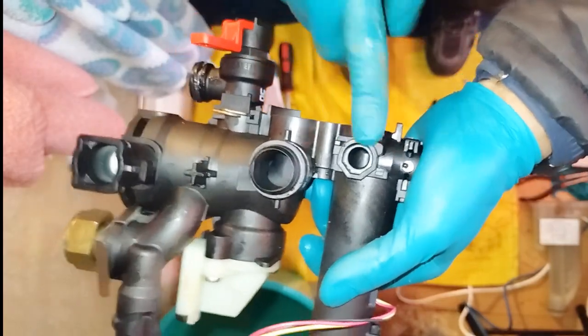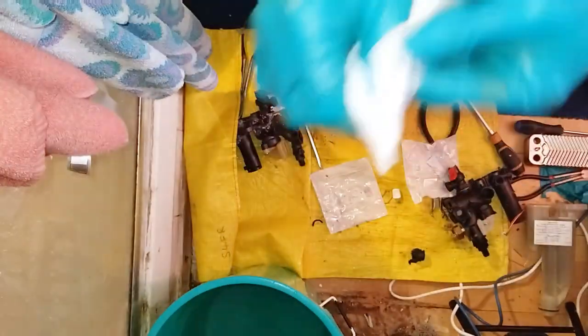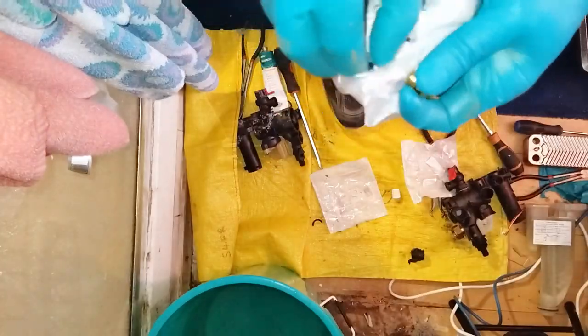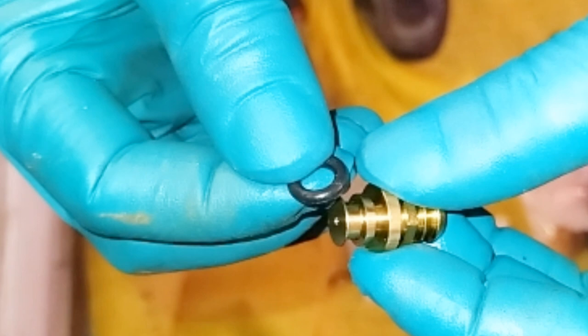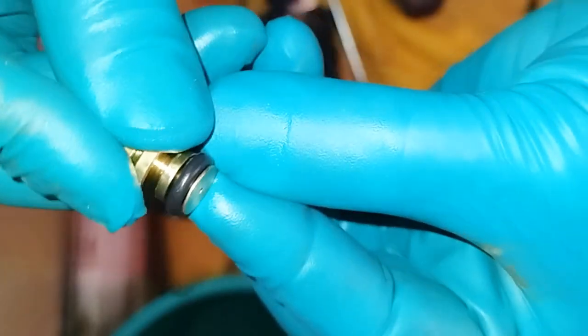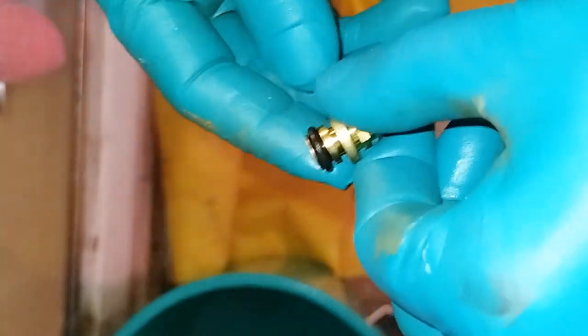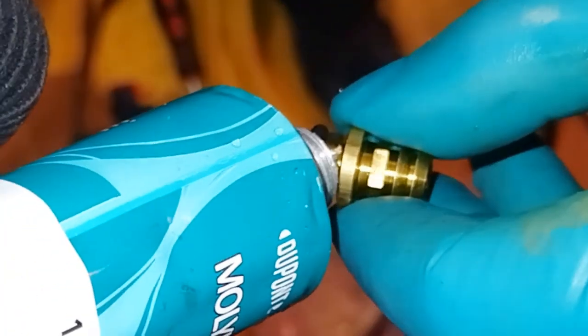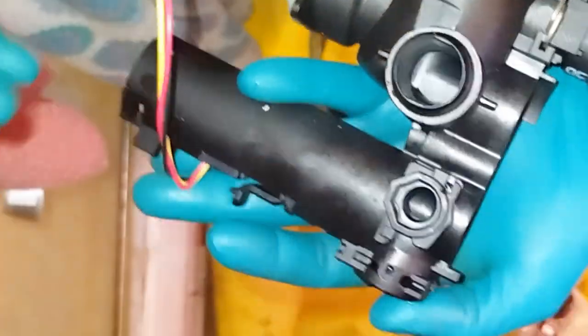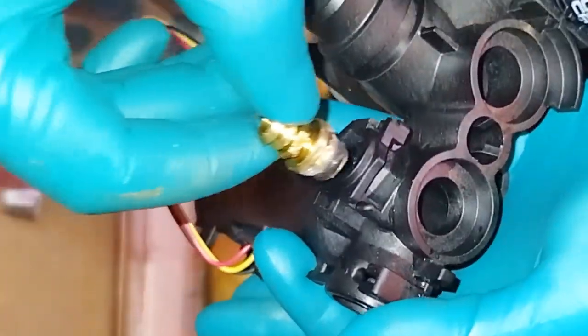Okay, there is a little fitting which goes in this space. Never forget this, because I've forgotten it once in the past, and I finished everything, and as soon as I started to fill it up, there was water everywhere. So this is the little brass fitting which goes in there with the little O-ring, which you can't miss. There is only probably one or two of the same size, the smallest O-rings, which go onto this little brass fitting, which goes in there. O-ring goes in, push it in.